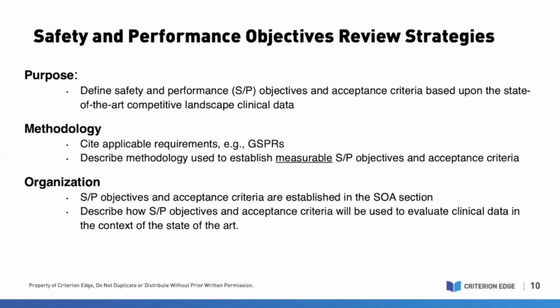Remember, safety and performance objectives and criteria must be based upon the competitive landscape data analyzed in the state-of-the-art section. Be sure to fully describe how those endpoints and criteria will be used to then evaluate the subject device's clinical data in the context of the state-of-the-art.